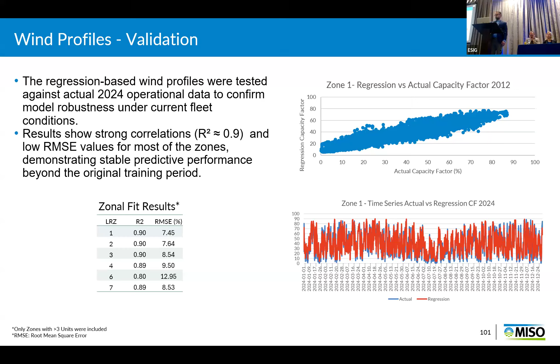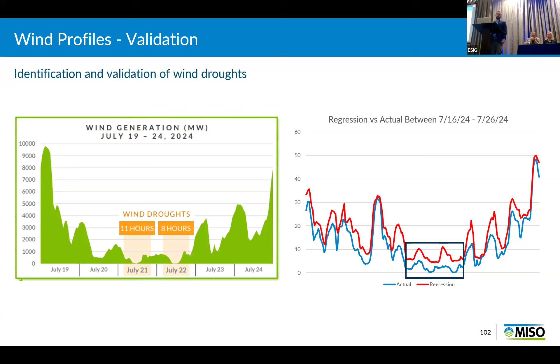And then the really important part for us is identifying and validating wind droughts, because in the end what we're trying to do is identify when the risk is happening. So this is showing the regression versus the actual during one of those wind drought times, which was July 19th to 24th in 2024. You can see that it does identify it, but there are also areas here for improvement. The red is the regression, and it's pretty consistently above what the actual was. So there are areas to make more improvements - is it cut in speed? Is it granularity on where they are located? There's different things we're looking at to better address those.